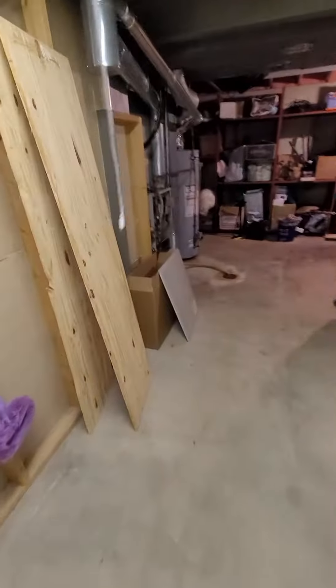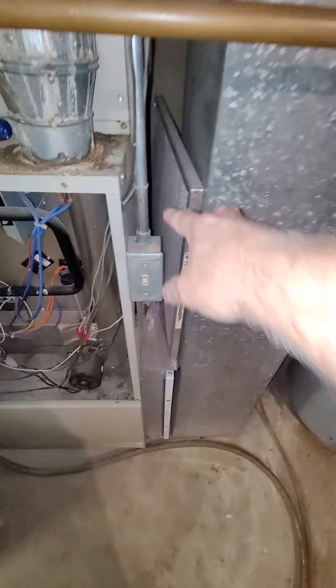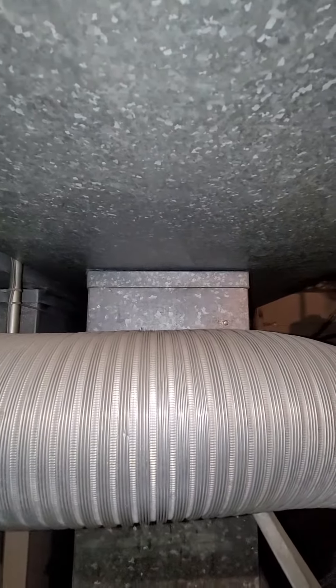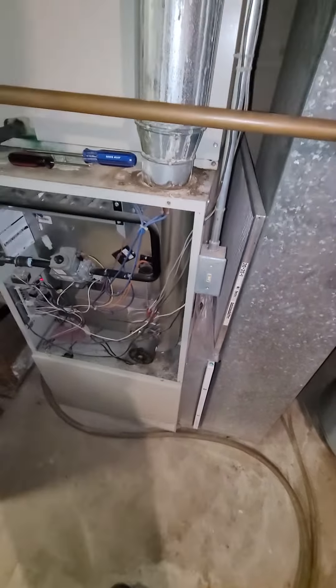The unit itself is right over here. As far as space, we're a little tight here. On the return drop we've got room — we can scoot that over to the right, plug that up, and then run that down to open up the space and put the five-inch filter cabinet in there.